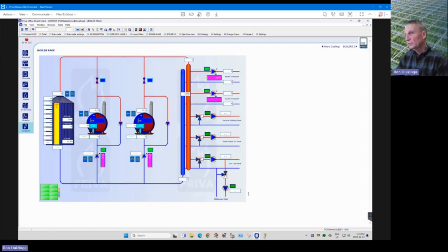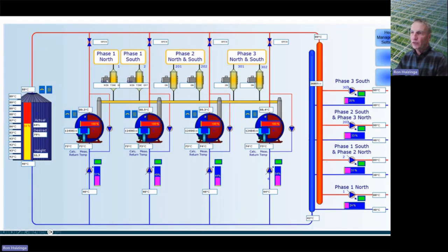And then there's another thing to consider, which is how big the fans are. In that picture I had here, these CO2 fans that are sucking off here, if they are smaller than the capacity of the exhaust of that boiler, you can watch the exhaust of the boiler when your boiler is running full speed and your CO2 fans are on.